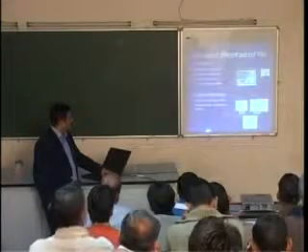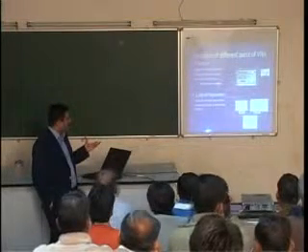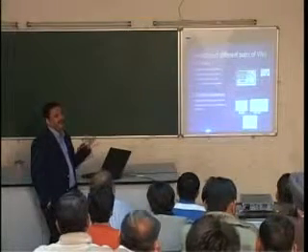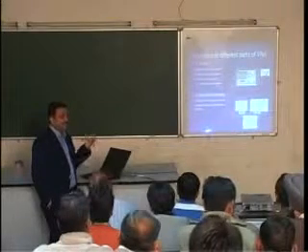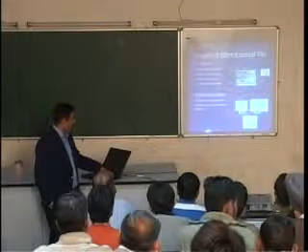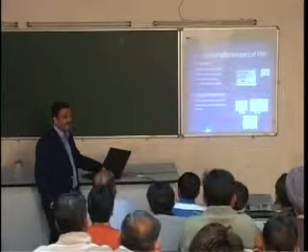Then you have 2-port VNA, 4-port VNA, and different types. But the basic thing is this is how it looks, and you have a source inside and a signal separation. Even when we are measuring a 4-port device or a 6-port device, the amplitude and the phase information of the source has to be the same at each port. Otherwise we are going to have different reference signals, because in all our measurements we are always talking about A by R or B by R.